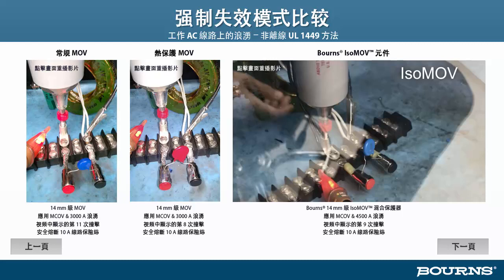Okay, third movie. The one on the right is a Bourns IsoMOV protector. This is a 14mm device as well, and we again apply the maximum continuous operating voltage to the device. The surge we are applying is 4500 amps, 50% larger than the surge applied to the previous devices. We're looking at the 9th hit in the video. Again, the 10 amp fuse blew. Now hopefully you saw that little bit of smoke. Let's go ahead and replay that again so you can take a closer look at that. You can see there is a tiny pinhole in the epoxy where just a little wisp of smoke escaped.